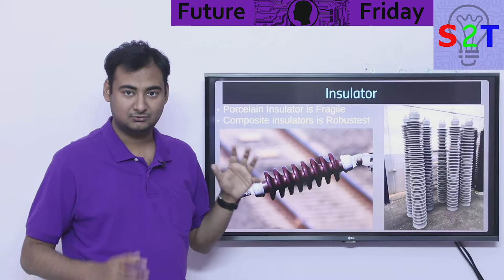On top of that, if you are familiar with high voltage systems, you must understand - check my last episode - that circuit breakers need intelligence, circuit breakers need sensors. Now in a normal old school substation, you have what we call a current transformer and a voltage transformer. These puppies are big, oil filled, very expensive, space consuming equipment.